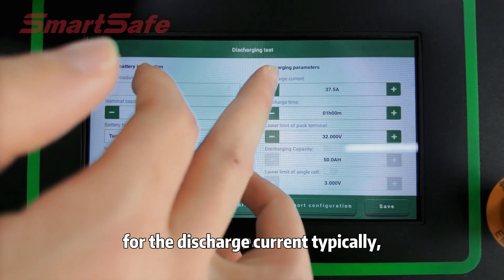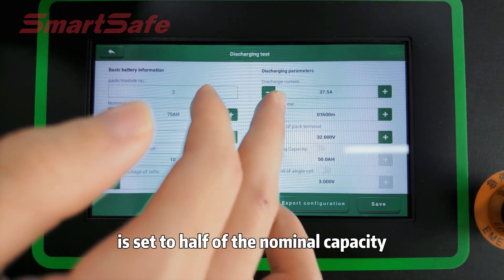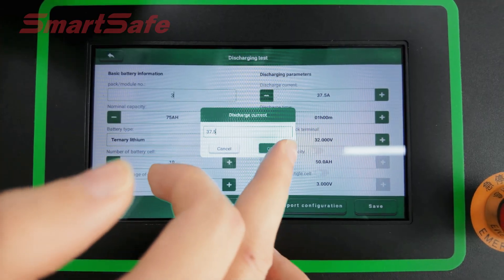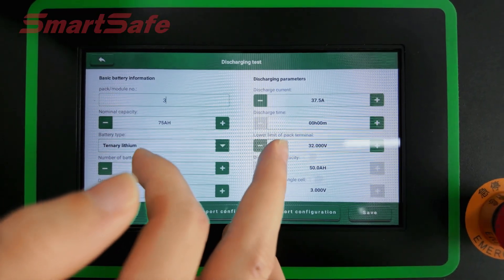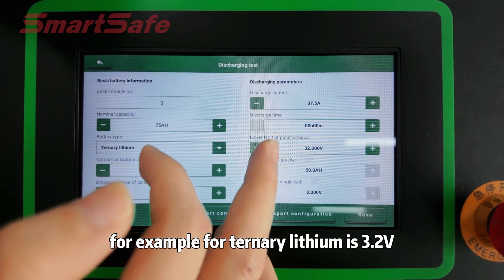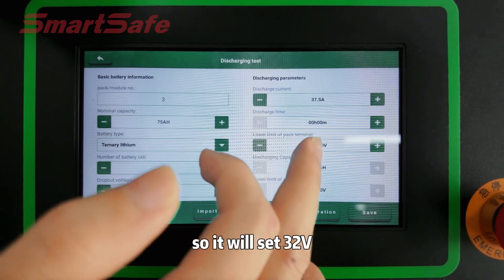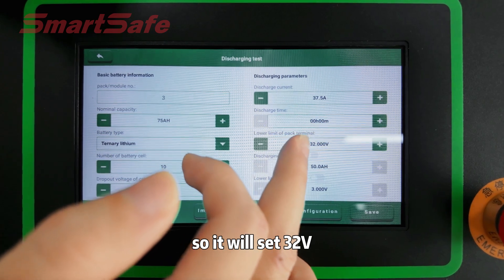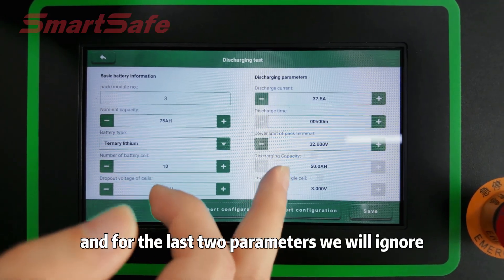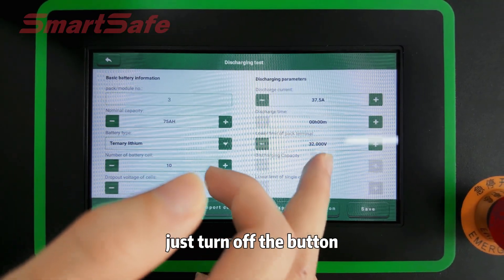For the discharge current, typically the standard discharge current is set to half of the nominal capacity, so we will set 37.5. For the low limit of the pack terminal, this is the lower limit for a single string multiplied by the number of cell strings. For example, the terminal cutoff voltage is 3.2V, so we will set 32V. For the last two parameters, we will ignore them — just turn off the button.